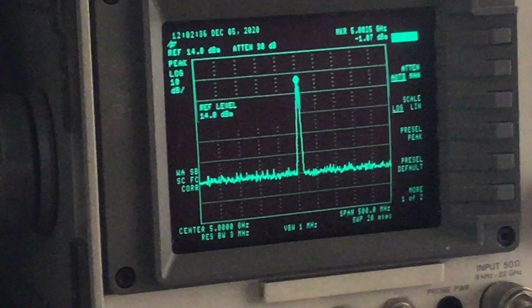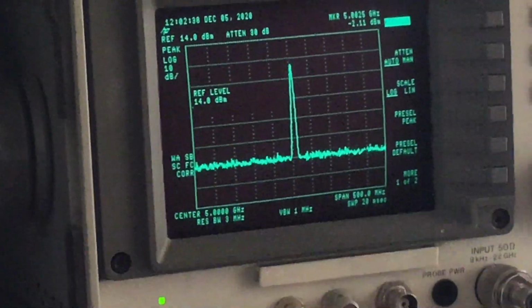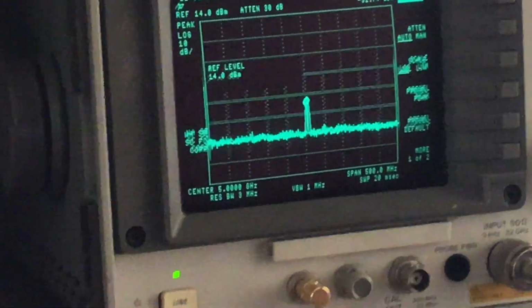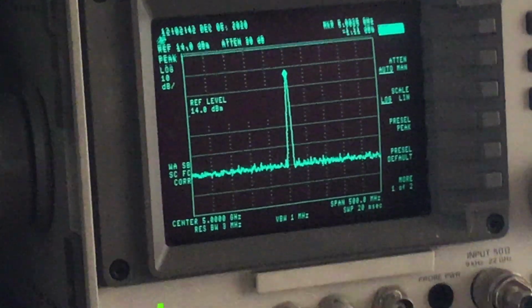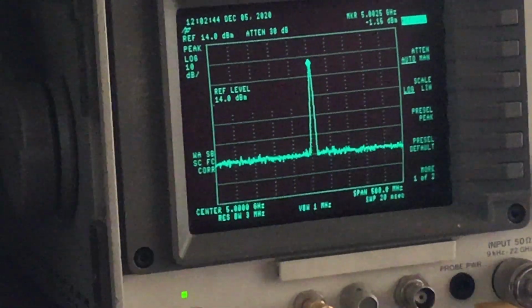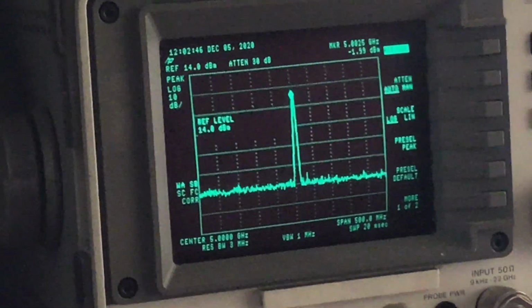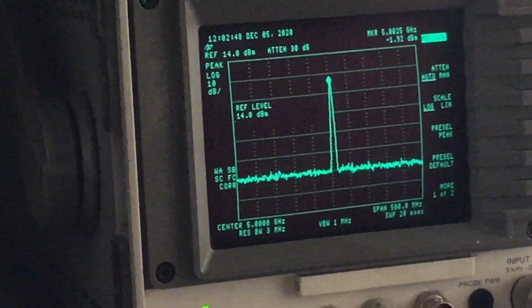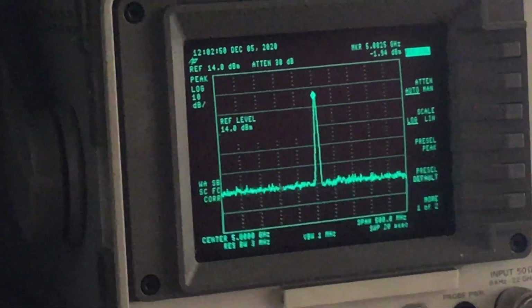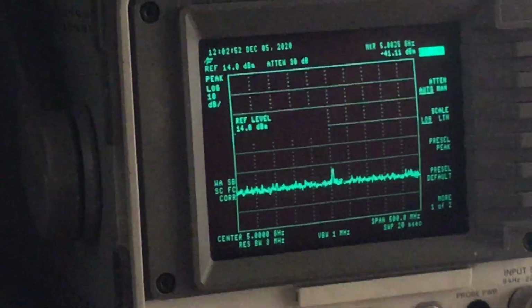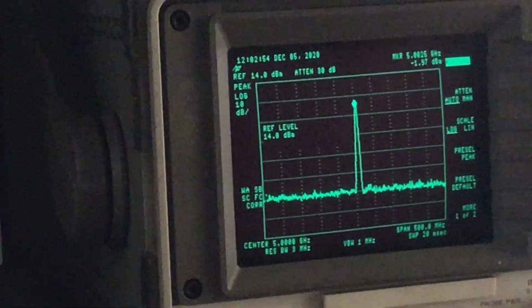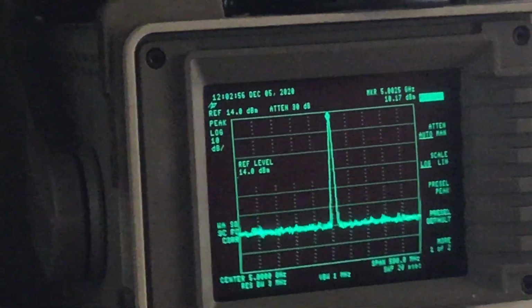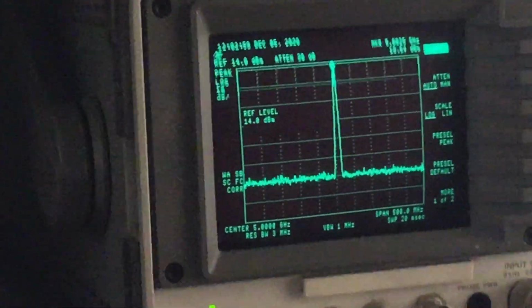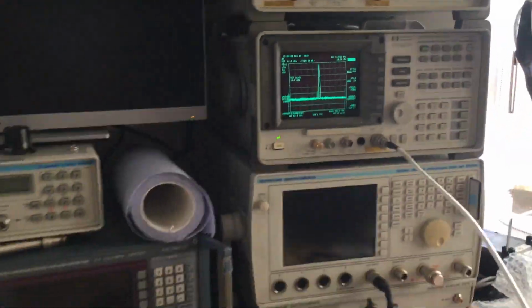So it's only when you step attenuator, you can hear there clicking in, where it jumps, you see. So it's not adjusting the RF level really. It's getting to a certain level and then just jumping with the step attenuator. So we'll set that to 0 dBm again, and it's at 10 dBs higher than it should be. So this means we need to do a calibration.